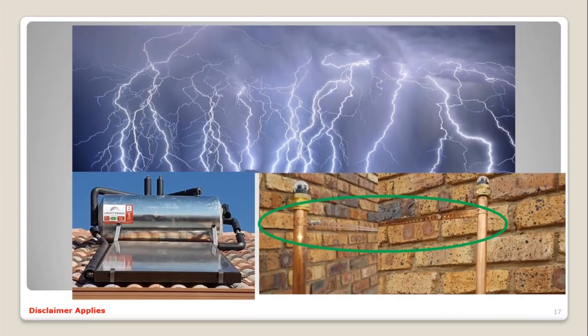And this also addresses solar water heaters that are installed on the outside and heat pumps. When you do come across a replacement of a solar water heater or heat pump, do make sure that you do see that the earthing to the bonding is being done, and that it is sufficient, and also to note to the homeowner that it's been checked. Because in some cases where there is maybe a lightning strike onto a geyser system and the geyser got faulty, they need to get somebody out to retest that earthing to the DB again, as it could have damaged the earth wiring to the distribution board.